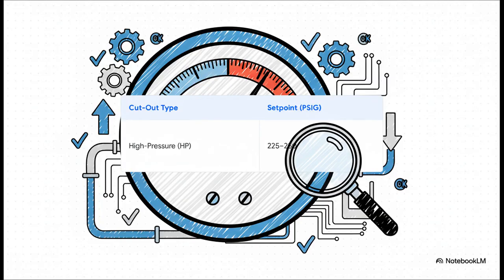Now, here's where it gets really cool. The precision involved is just incredible. Look at that table, the technician isn't just checking if it works. They're making sure it trips within that super specific window, between 225 and 250 psig, that's pounds per square inch gauge. That number comes straight from the OEM, the original equipment manufacturer, the people who built it, and the test has to be perfect.